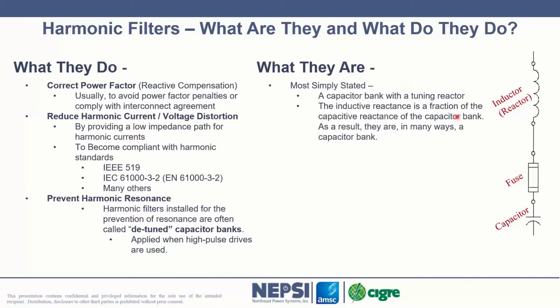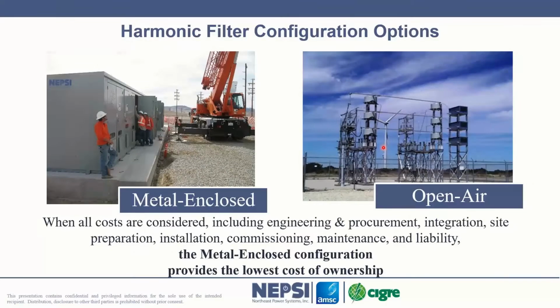So most simply stated, what are they? Well, it's a capacitor bank with a tuning reactor. And so that's what you see here. Very simple, we're putting a tuning reactor in there. So we're going to be talking about those two plus resistors. It's also important to note that oftentimes harmonic filters come in basically three configurations. One configuration consists of the metal enclosed solution. This is what NEPSI does. This is what we developed our company upon. It's a fully integrated solution.